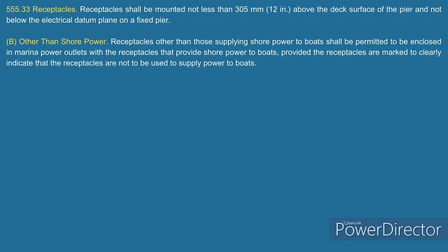I looked through this whole Article 555, and not once did I see anywhere that it mentioned any other equipment having GFCI protection. It all deals with receptacles and the receptacles that are installed in the outlet. In this case, it says enclosed in a marina power outlet. Just to keep it in layman's terms, you could have two receptacles in this box, in this outlet: one receptacle outlet that has 30 milliamp GFCI protection, and one that has 4 to 6 milliamp GFCI protection. This is basically saying you can have those enclosed in the same box as long as you mark that the receptacle with the 4 to 6 milliamps is not to power boats.